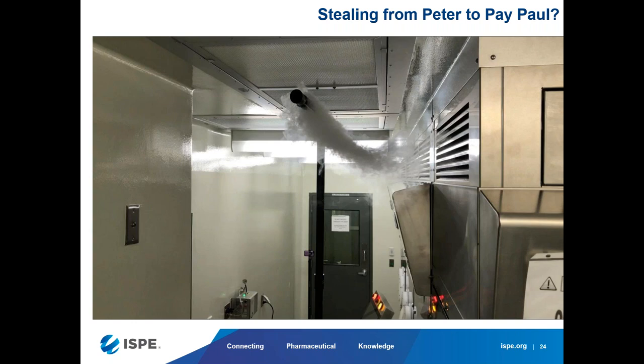But what happened? The inlet grill is right next to the HEPA filter. So we are stealing from the HEPA filter, the LAF part, to feed the RABS. And what happens underneath? We wanted it to be clean because from here we will be going into grade A. Did we keep it clean? No, the air does not even reach halfway.